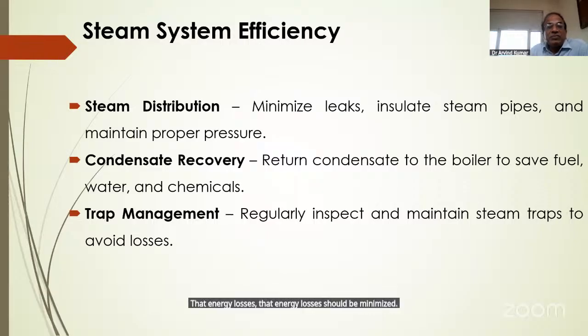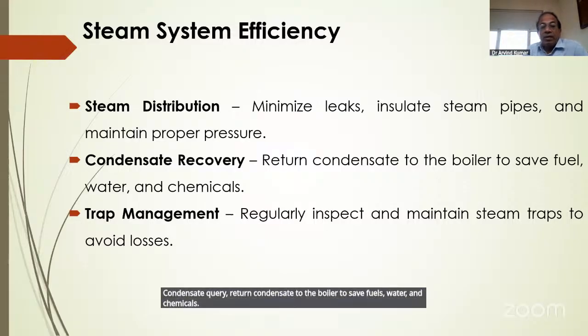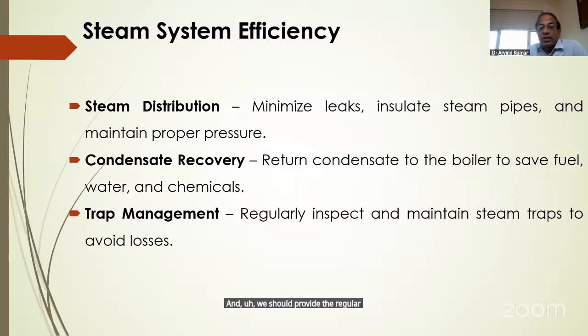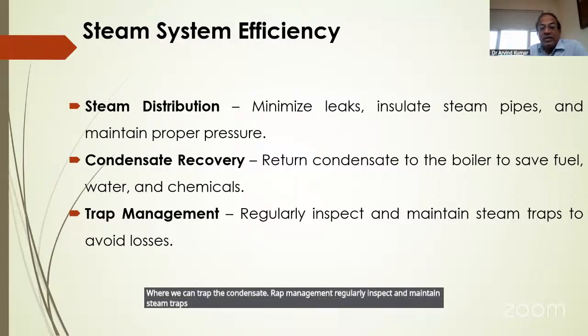Now, the third one is steam system efficiency, steam distribution. Minimize leaks in the energy distribution network, and steam pipes should be insulated, maintaining proper pressure across the length of the steam pipeline. Condensate recovery: return condensate to the boiler to save fuel, water, and chemicals, and we should provide regular intervals where we can trap the condensate. Trap management: regularly inspect and maintain steam traps to avoid losses of steam.